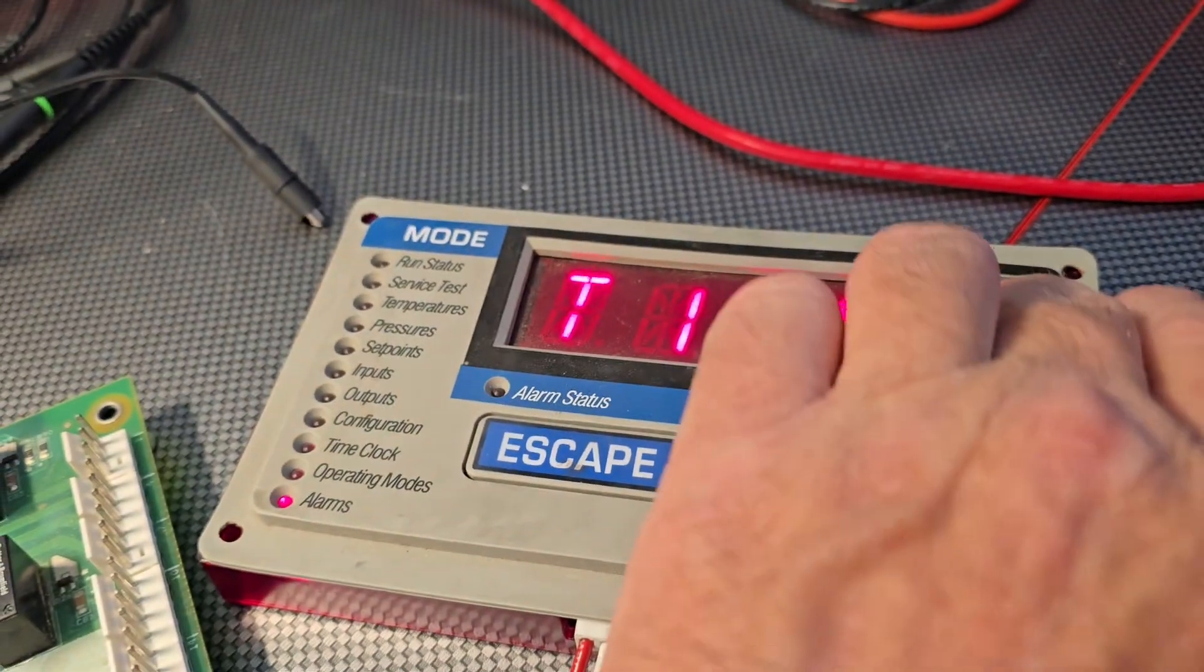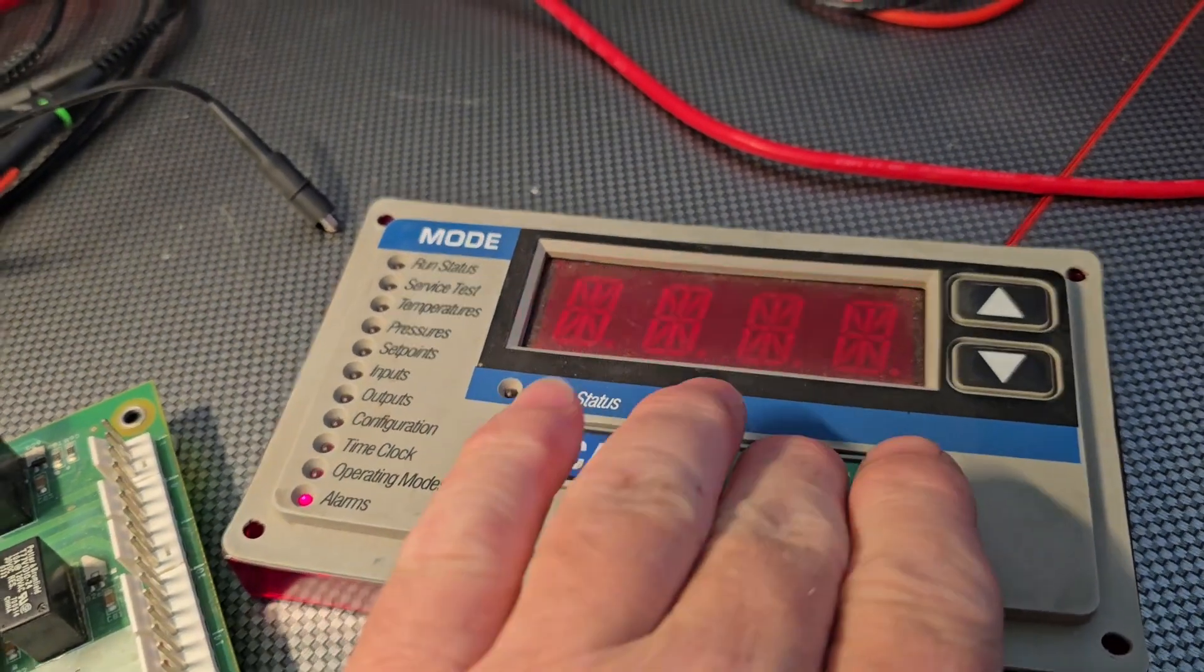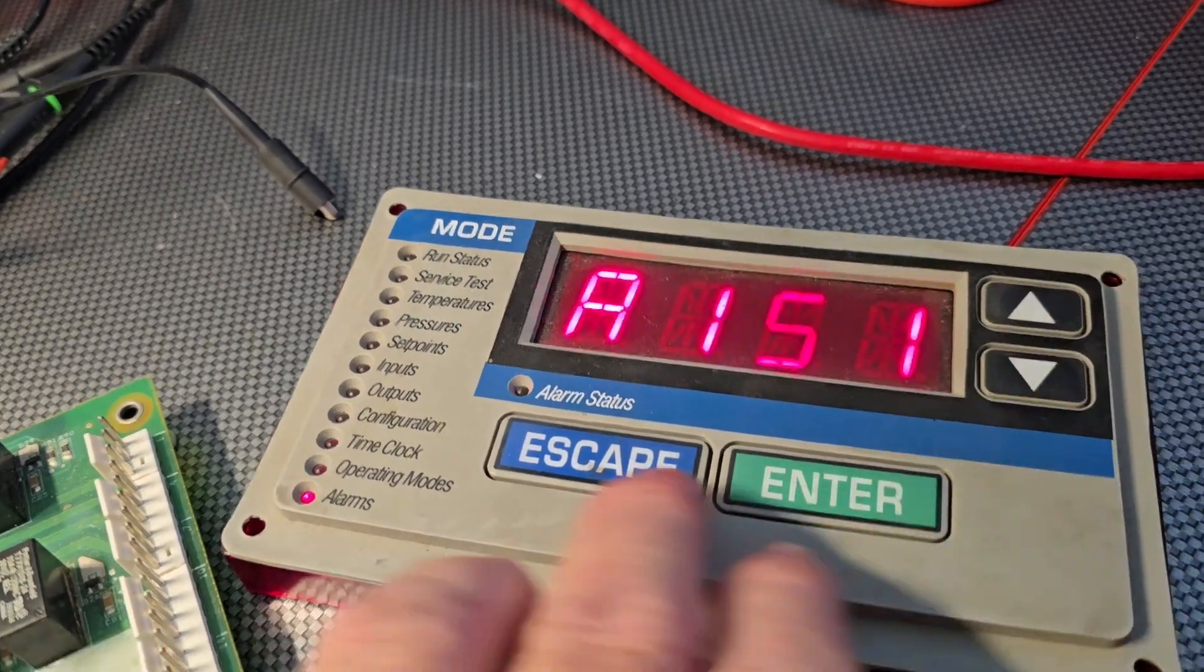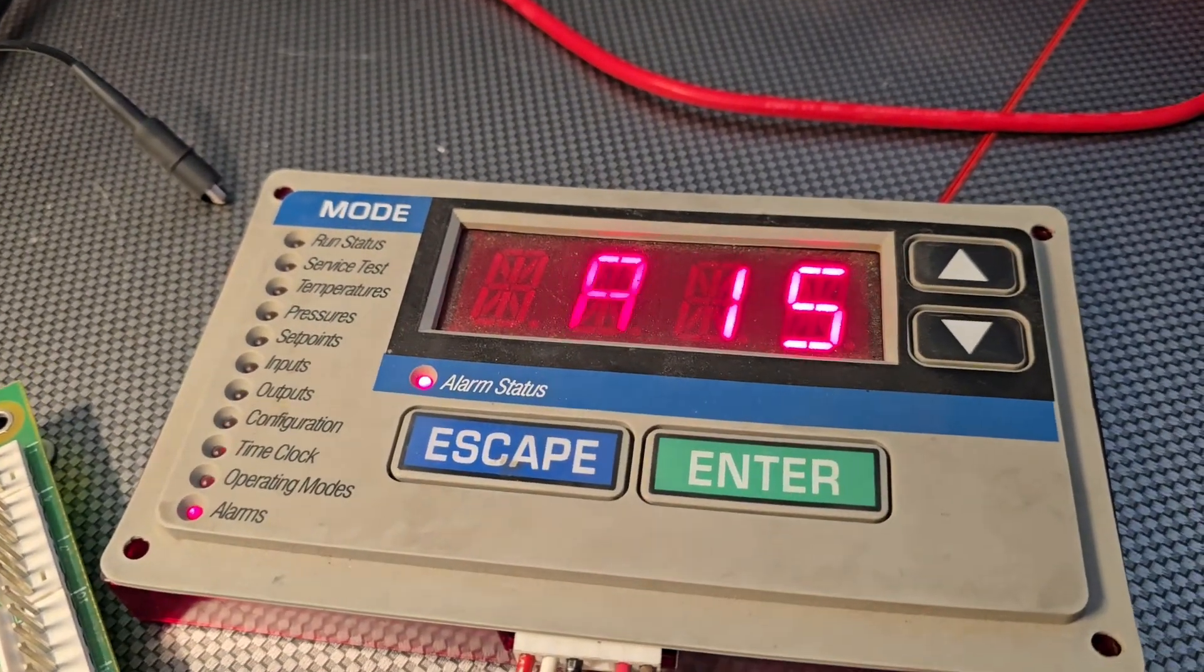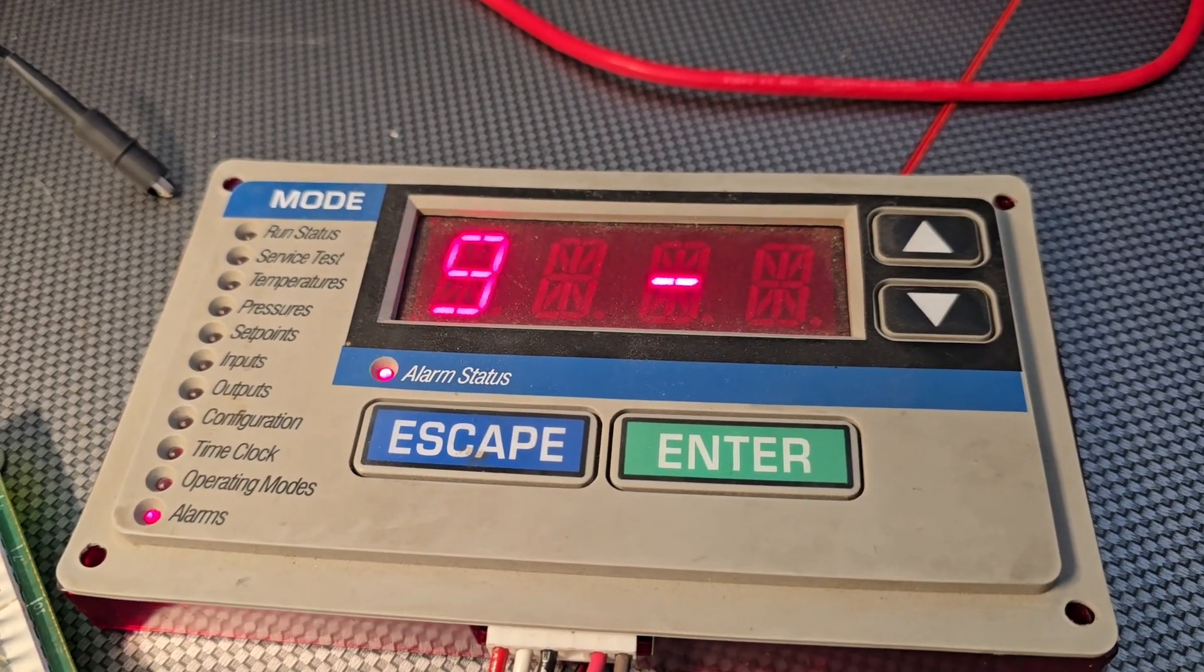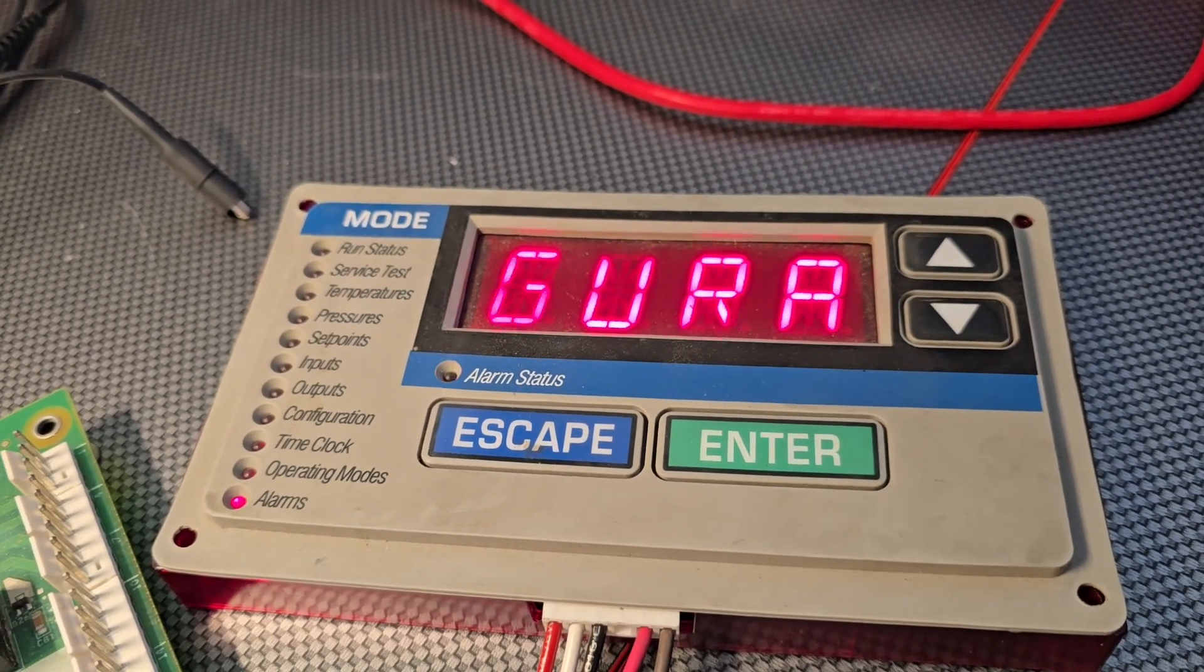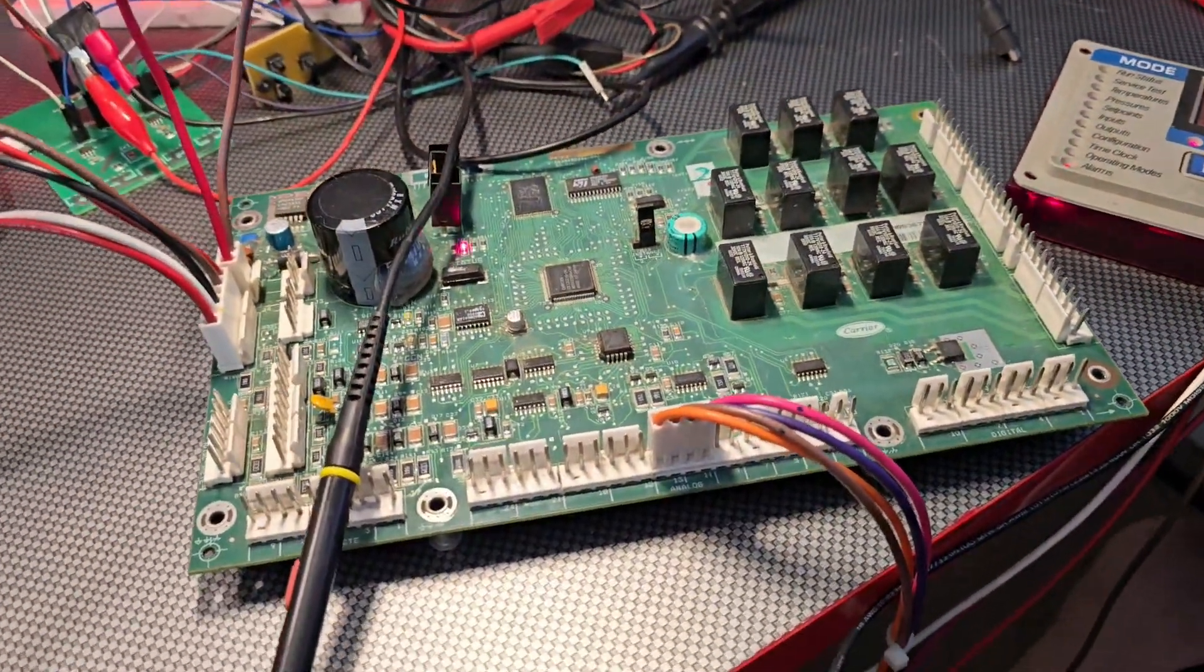Failure. That one was not familiar with. So we go to history. How is that the only alarm in here? Huh. Well, there's an A151 and you go, what's that? Oh, there's the date time 01/01/99 at 00:30:12:31 in the morning. Illegal configuration. I wonder, this thing's probably all full of corruption.